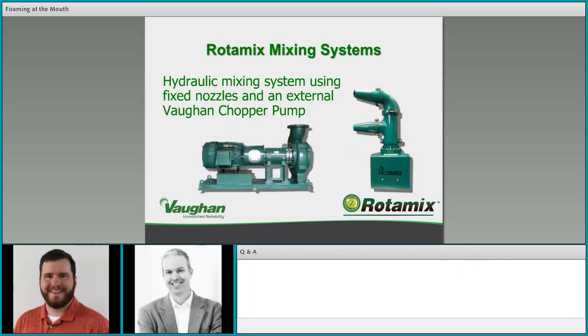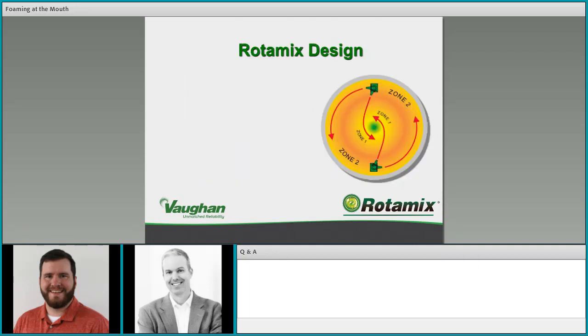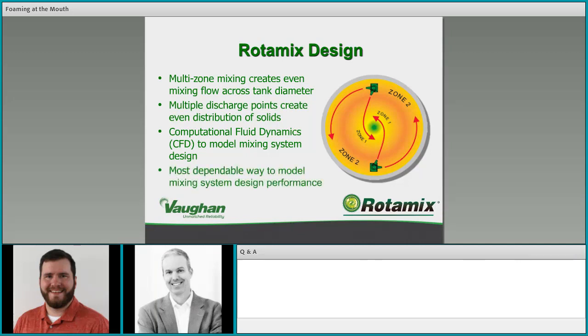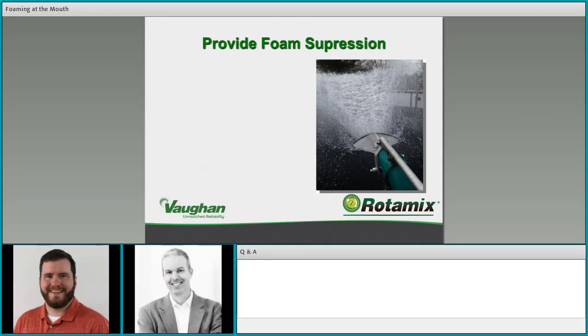A brief description of Rotamix mixing systems: it's a hydraulic mixing system using fixed nozzles and an external Vaughan chopper pump. The design is multi-zone mixing, which creates even mixing flow across the tank diameter using multiple discharge points and even distribution of solids. We use computational fluid dynamics to model mixing system designs, ensure performance, and meet design specs for optimal mixing flow in your digester volume. It's the most dependable way to model mixing system design performance before you put the system in.